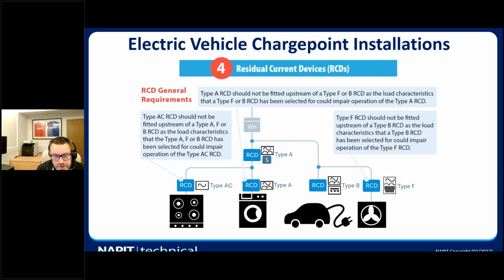And we have an example of the general requirements for RCDs. So you're looking at the different types of RCDs and where you can install them, the hierarchy of the RCDs. Installing a Type A has got to be installed right back to the system. If you install Type Bs, they can be before Type A and all the different types on there. At the time of the audits, some Type A RCDs may have been installed, but now, with Amendment 2, it's all Type A's that will be installed for EV charge points. You can't install AC on any EV charge point.